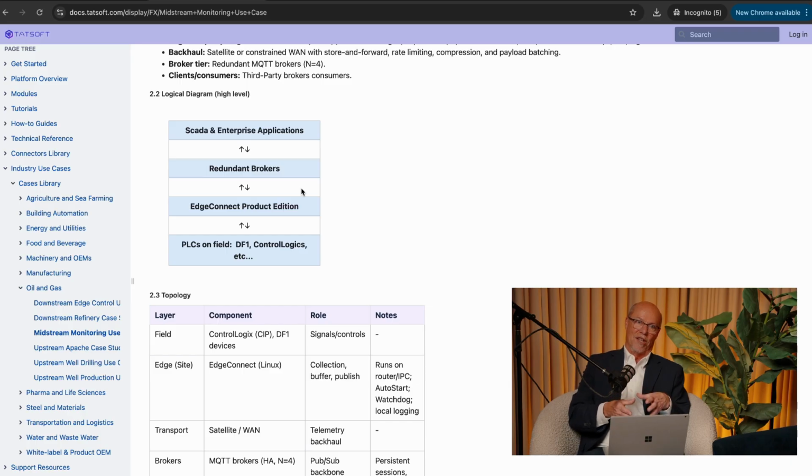Then we packaged that up and prepared it to go to a series of 4 redundant MQTT brokers at the data center, where that was connected to their main overall SCADA control system. The SCADA system used that architecture to go down and individually supervise, collect data from, and control those individual stations.